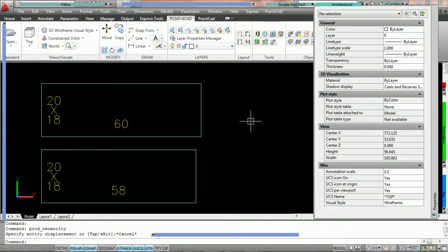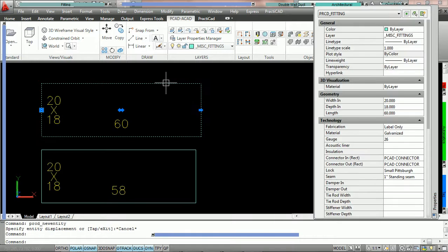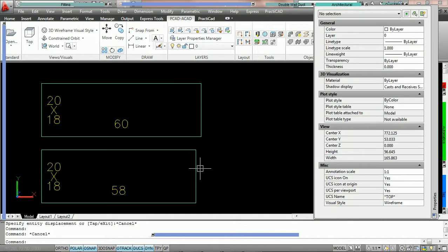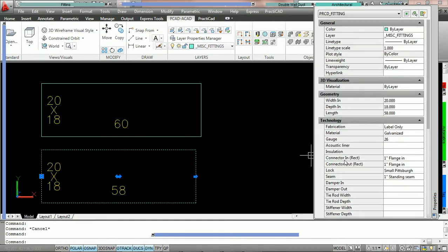What we have on the drawing are 2 pieces of duct. The first piece of duct, if we click on it, you can see that the connector is PCAD connector for the in and the out. That is the connector we designed with the 2-inch connector flange. The second piece of duct on the drawing we're going to click on, you can see this duct was placed with a 1-inch flange in on the connector in and connector out.